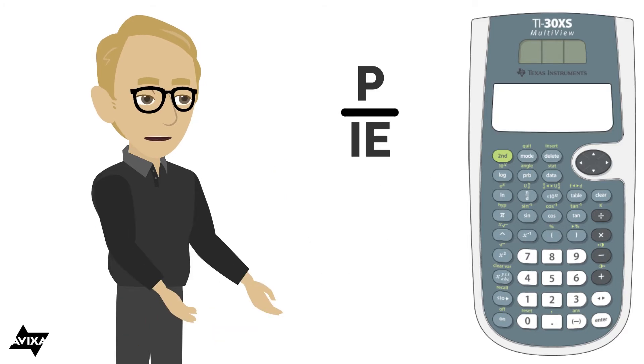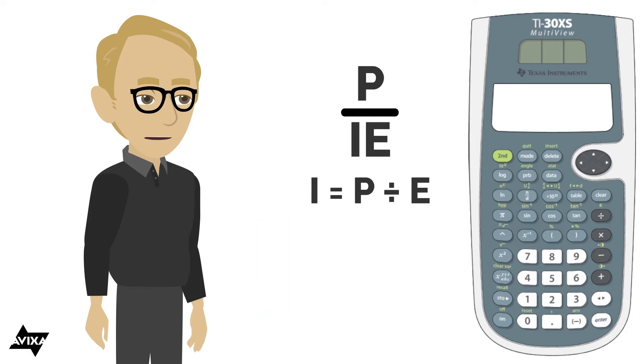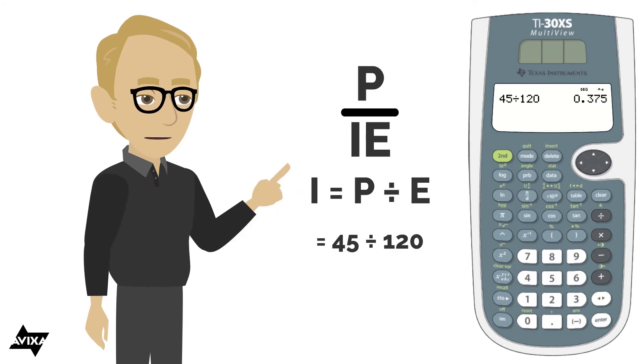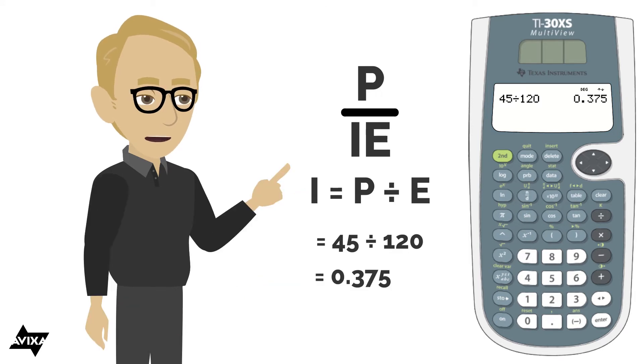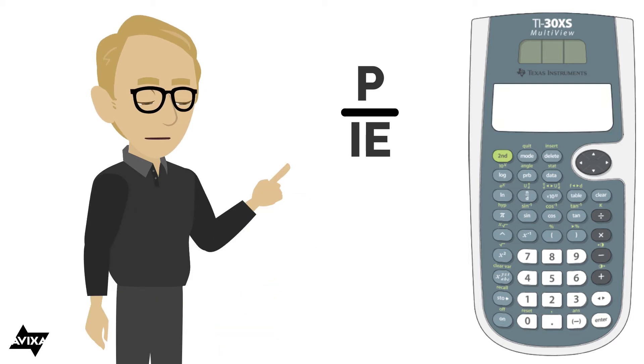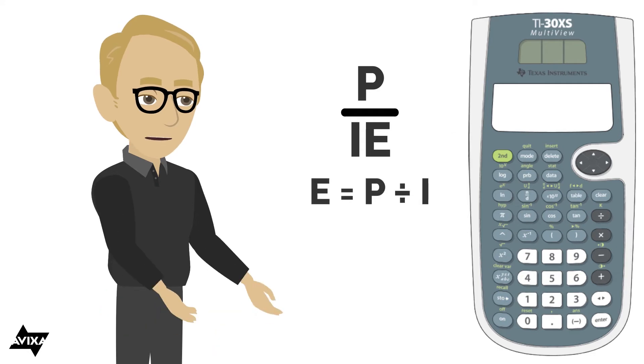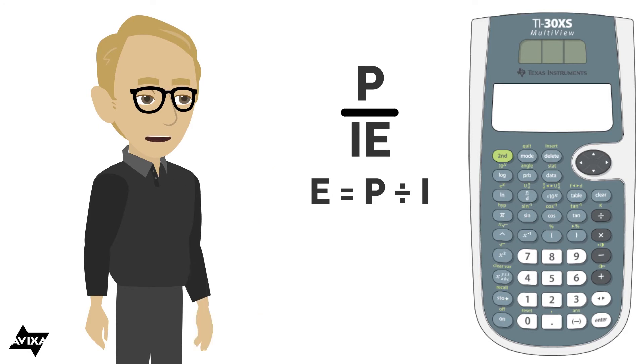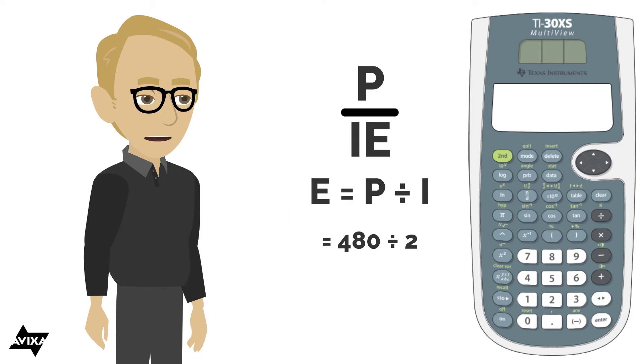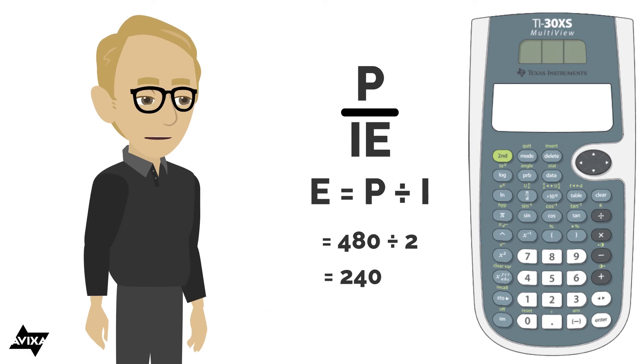Let's do current — that's power divided by voltage. The power is 45 watts and the voltage is 120 volts. 45 divided by 120 tells us we are drawing 0.375 amperes of current. And one more: voltage equals power divided by current. The power consumed is 480 watts and the current draw is 2 amperes. 480 divided by 2 tells us the voltage in this circuit would be 240 volts.